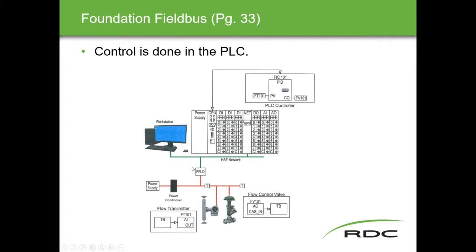And the idea is that this is in the field, so you've got to have shielding and twisted pair and all that kind of wonderful stuff, so you don't get EMF disruptions. And then the HSE network is a high-speed data transfer between the controller and the workstation. Gotcha. Thank you.